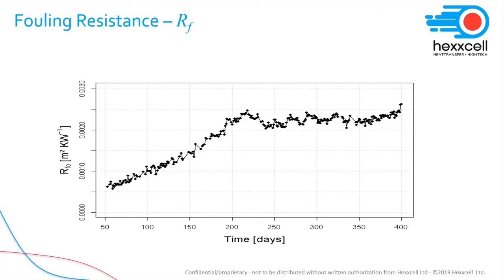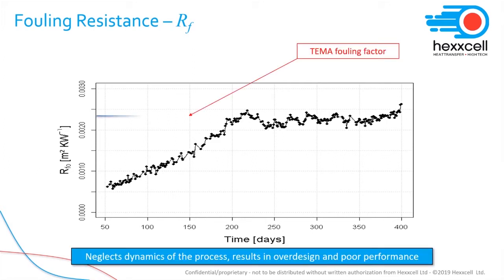Well, it is clear from looking at the plant data that fouling evolves over time. So if you design a heat exchanger using a fixed fouling factor, you're neglecting the dynamics of the fouling process itself, as you're assuming that the fouling resistance is the same at time 0 when the heat exchanger is put clean into operations, and at the end of run when the heat exchanger is actually fouled.